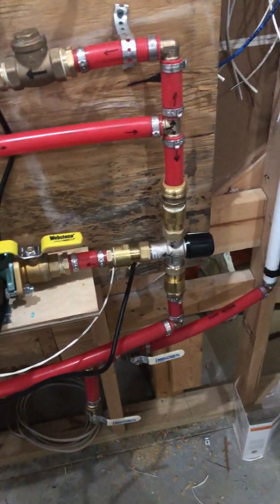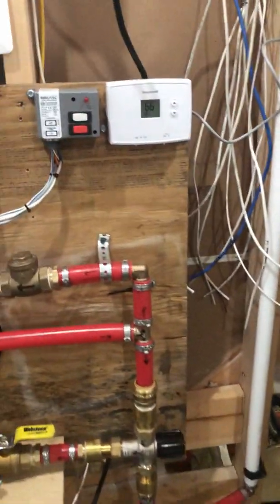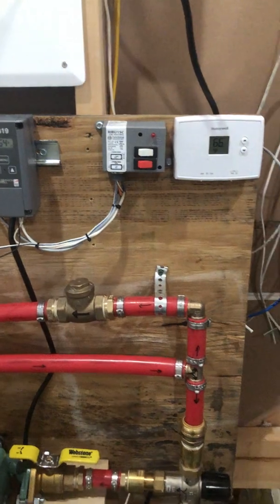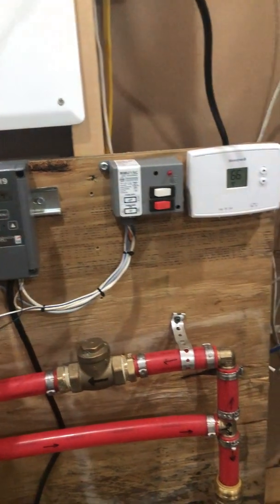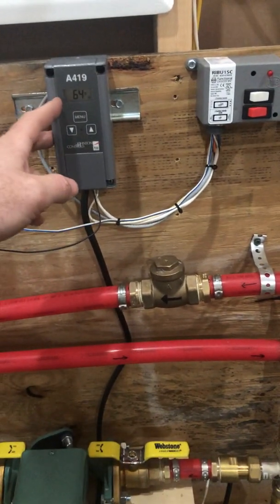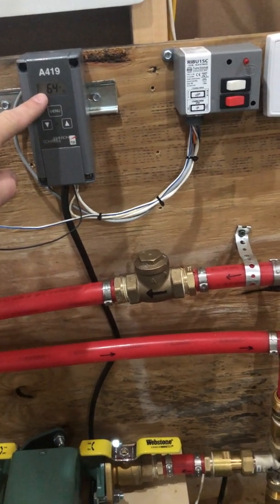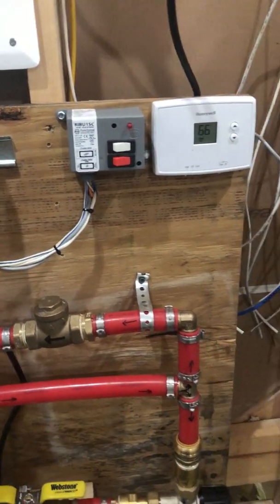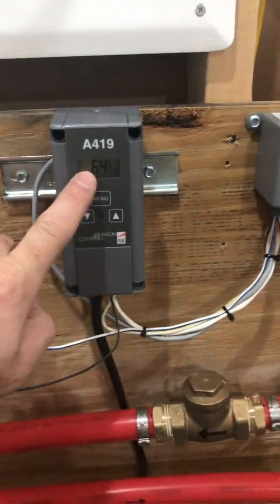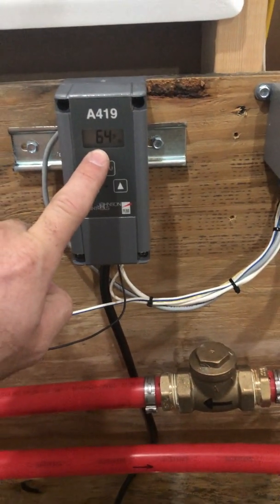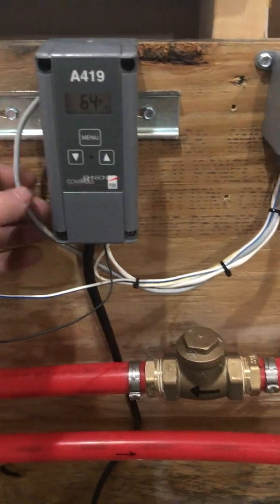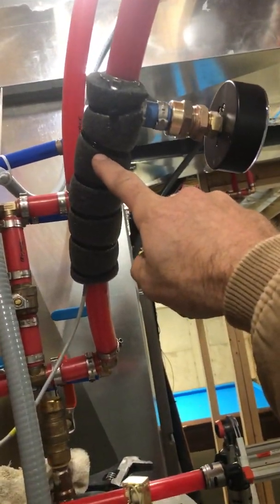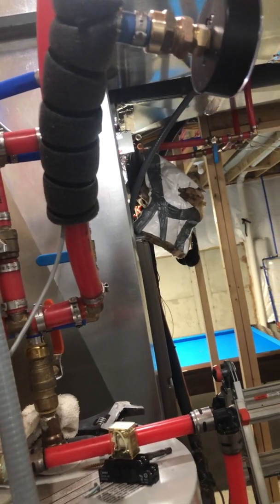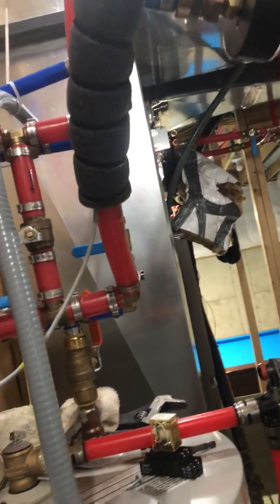It's not gonna hurt anything. So I'll talk about the controls just a little bit. This is almost fully set up. Here's the second Johnson Controls Aquastat. So what this one is going to do is, right now the water temperature that it's reading, and the probe is not actually in, and so there's a slight discrepancy between this number and the number outside, and that's okay. But this gray wire is the temperature probe, and I have it strapped to this pipe, so it's not getting the most accurate reading, but I tried to make it as close as I could.